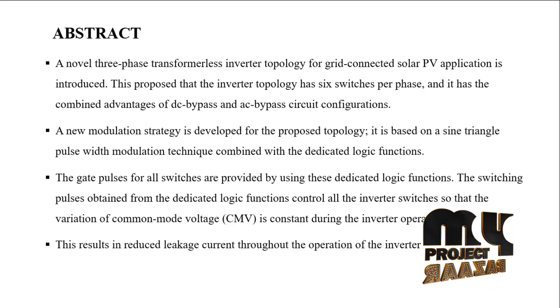A new modulation strategy is developed for the proposed topology, using sine triangle pulse width modulation techniques combined with logic functions. Gate pulses for all switches are provided using dedicated logic functions, which control the inverter switches so that the common mode voltage remains constant during operation, reducing leakage current throughout inverter operation in the PV panel.